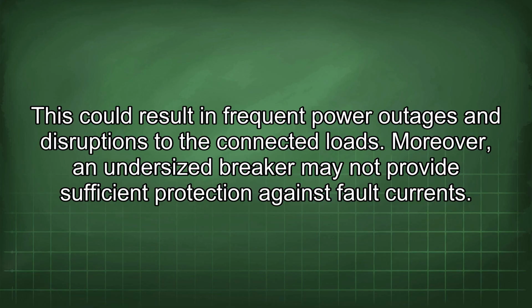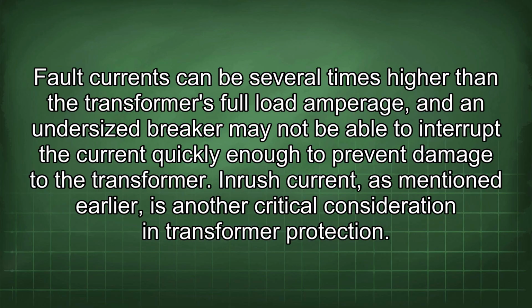Moreover, an undersized breaker may not provide sufficient protection against fault currents. Fault currents can be several times higher than the transformer's full load amperage, and an undersized breaker may not be able to interrupt the current quickly enough to prevent damage to the transformer. Inrush current, as mentioned earlier, is another critical consideration in transformer protection.